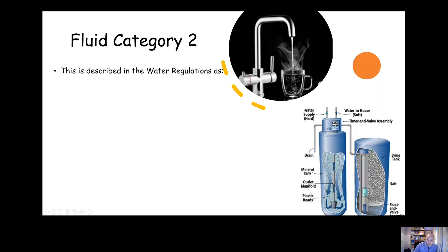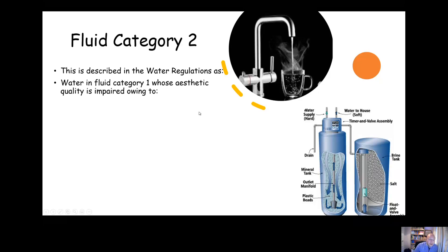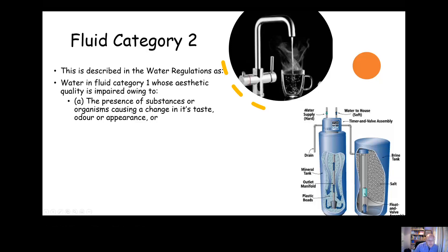Fluid category two is water which has had a slight change — described in the regulations as an aesthetic change. It might be something that's caused a change in taste or appearance. For example, if you got a cup of water from the mains and put a little bit of juice in it, you'd have changed it from the way it came in from the mains. It's still fine to drink, but its aesthetic quality — colour, taste, smell — has changed. Fluid category two isn't really a risk to health, but because it's changed from mains water you must put backflow prevention in place.